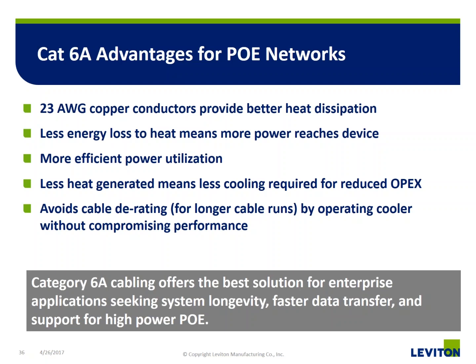Many people don't realize the 100-meter channels specified in both ISO and TIA assume a 20-degree C ambient temperature. As the temperature of the cable increases, you may have to reduce the overall length to ensure you're achieving the electrical performance required for that category.